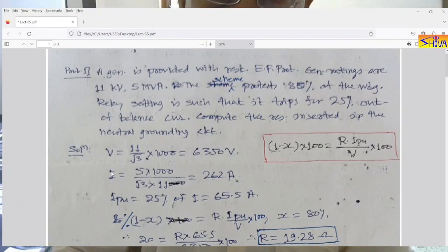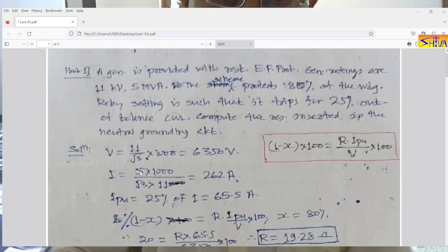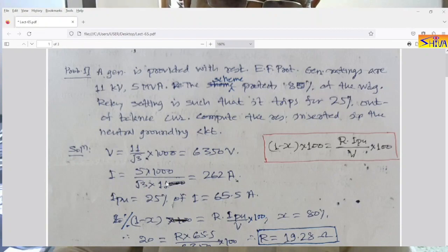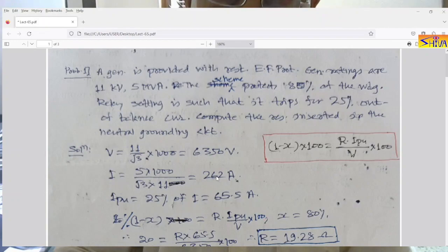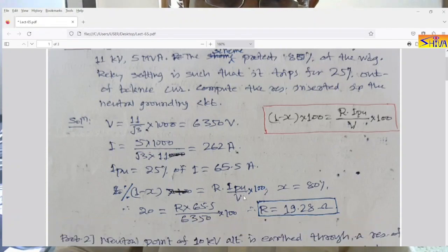For the current, we use the formula: root 3 × V × I = power. So for 5 MVA, converting to kVA: 5 × 1000 divided by root 3 × 11 kV gives current in amperes — that is 262 amperes. The relay pickup is 25% of the rated current, that is 25% of 262 A, so the pickup current is 65.5 amperes.